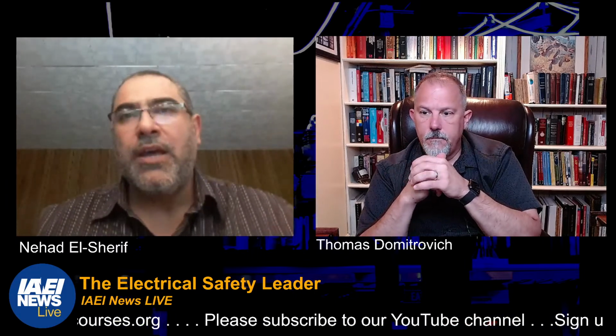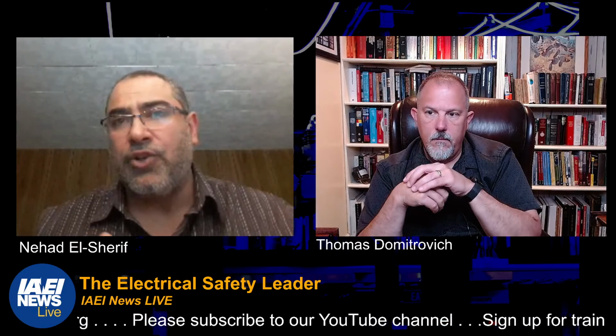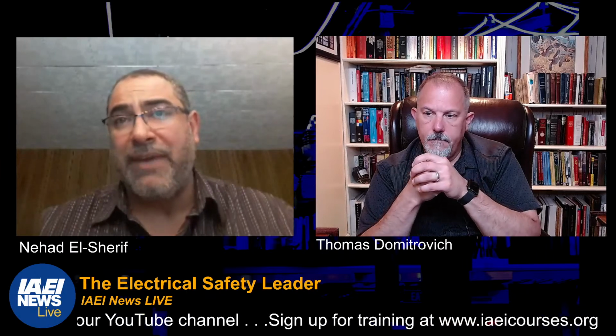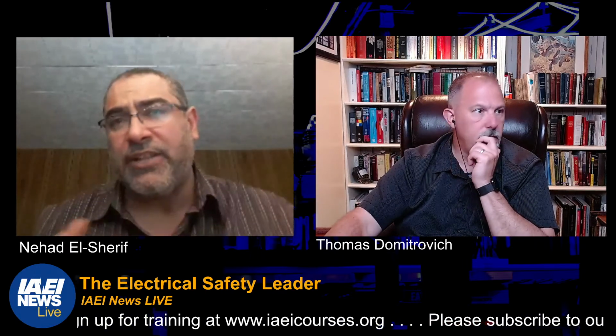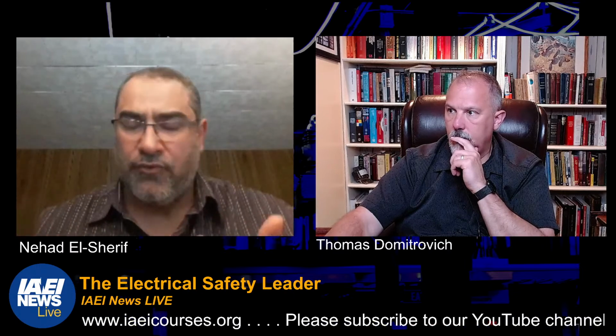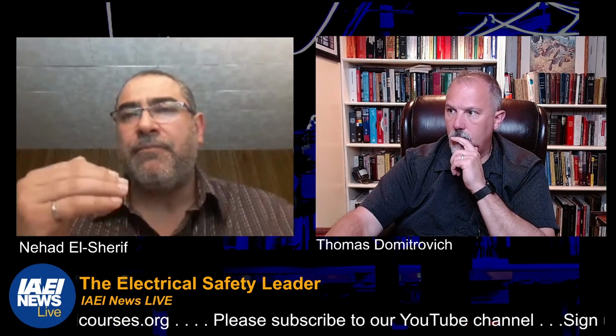Yeah, right, for sure. And Don Grenier has a good question. I don't know if you saw this, Tom. I did. Is it likely that special purpose GFCIs trip quicker than the maximum permitted trip time like GFCIs? I'll say absolutely. The equation that we showed here, Tom and I, on one of the figures, is the absolute maximum trip time allowed by UL. Manufacturers would trip quicker than this time.